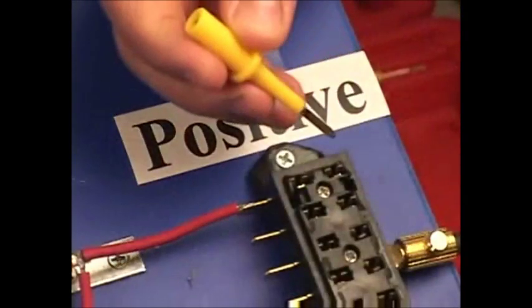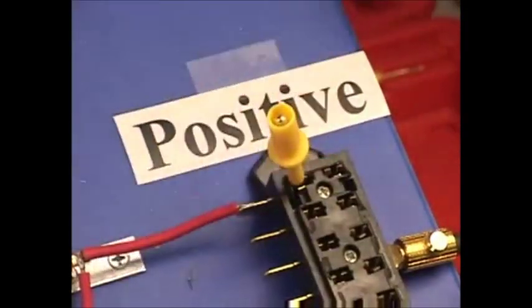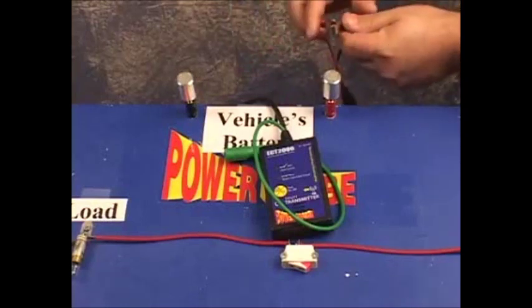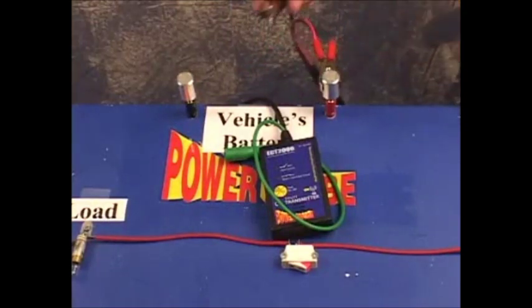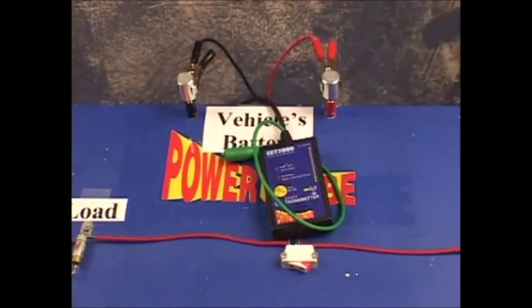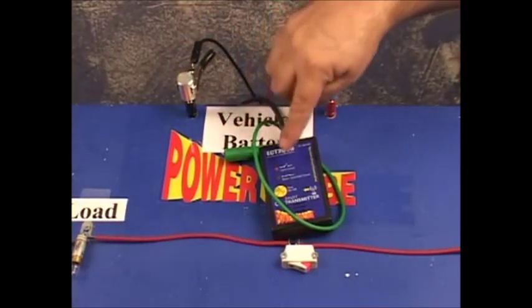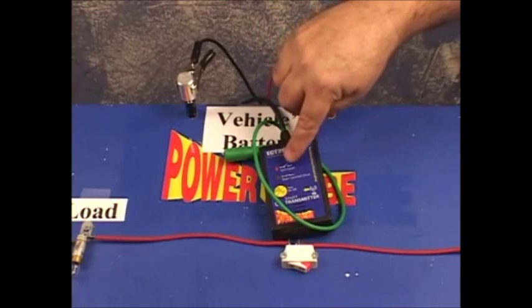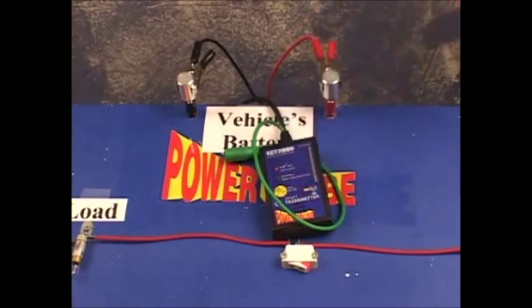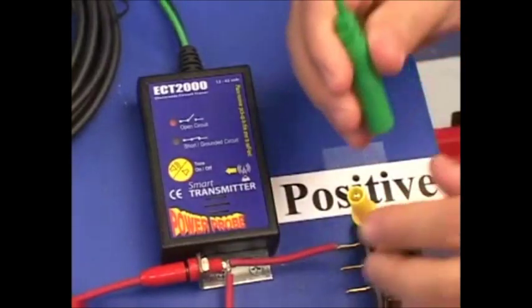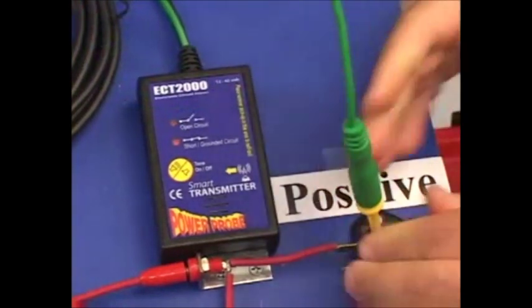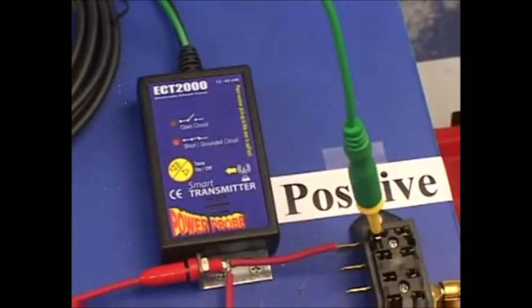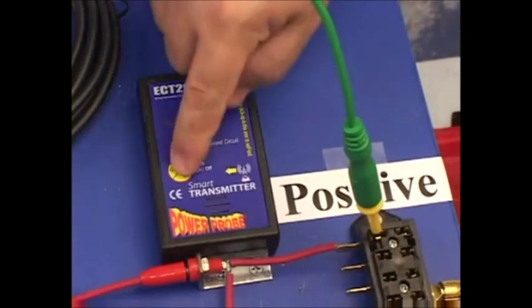Find the bad fuse, remove it, and connect the blade probe adapter to the shorted terminal. Connect the transmitter's power lead to the battery, red clip to positive, black clip to negative. The signal lead is open, so the open circuit indicator is on, and the tone default is off. Connect the signal lead to the blade probe adapter. The short grounded tone is now alerting us that the signal lead, which was open, is now seeing a grounded circuit. To turn the tone off, just press the tone on-off button.